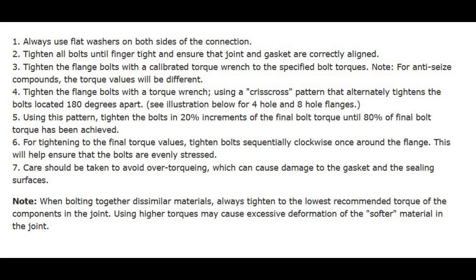Number 4: Tighten the flange bolts with a torque wrench using a criss-cross pattern that alternately tightens the bolts located 180 degrees apart. See the illustration for 4-hole and 8-hole flanges. Number 5: Using this pattern, tighten the bolts in 20% increments of the final bolt torque until 80% of final bolt torque has been achieved. Number 6: For tightening to the final torque values, tighten bolts sequentially clockwise once around the flange. This will help ensure that the bolts are evenly stressed.